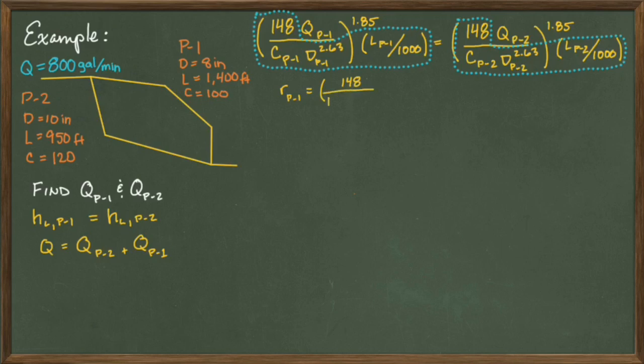Inserting the actual values for pipe 1, we get 148 divided by 100 times 8 to the 2.63 power, that whole quantity to the 1.85 power, and then we multiply that by the length of the pipeline of 1400 feet divided by 1000 feet. That, I compute as 1.2 times 10 to the minus 4th.